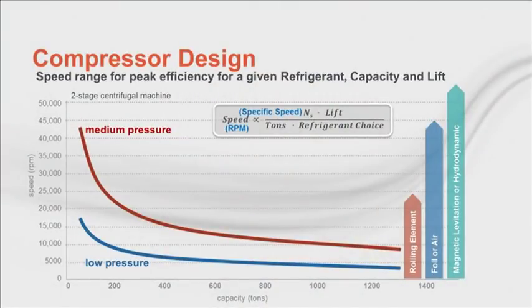The graph also illustrates the impact refrigerant choice has on specific speed and ultimately bearing choice. To achieve optimum specific speed, low-pressure refrigerant designs yield lower operational speeds than do medium-pressure designs. This results in more bearing choices for the compressor designers. The takeaway here is that lift, tons, and refrigerant choice are three primary inputs towards ultimately determining a compressor's efficiency. There are other inputs, but these are critical in that determination. Speed is simply an output that then drives bearing choice. If you want to significantly affect compressor efficiency, adjust lift parameters, tonnage, and select an efficient refrigerant.